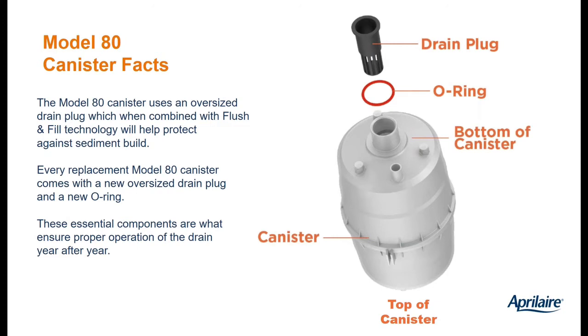Here's the canister viewed from the bottom. There's an O-ring to function as a seal — a good tight seal, no dribbling — and then the drain plug. The slots for the drain plug sit up quite high, which allows it to drain just fine even with a fair amount of sediment built up in the bottom. When you replace the canister, just like replacing an oil filter, make sure you get all of that O-ring off, and wet it before you seat it for a good tight seal. Every new canister comes with a drain plug and a brand new O-ring, made red so they're easier to see.